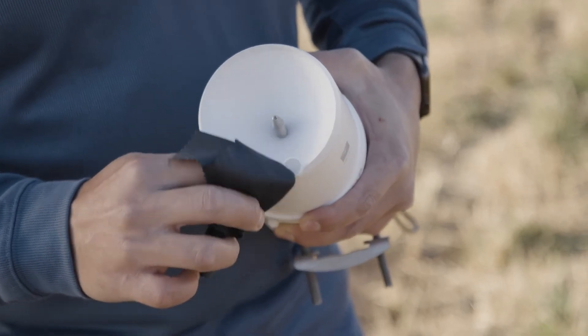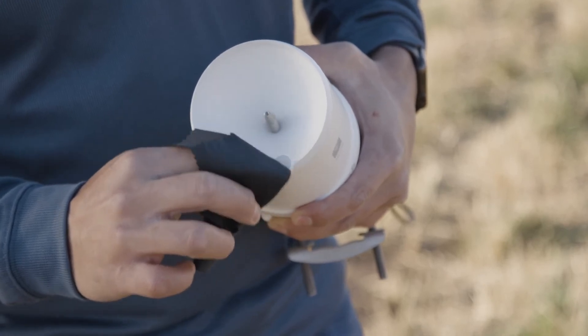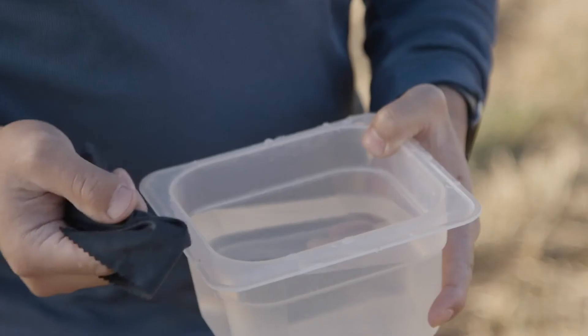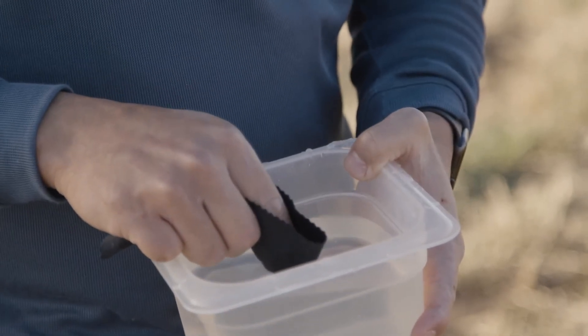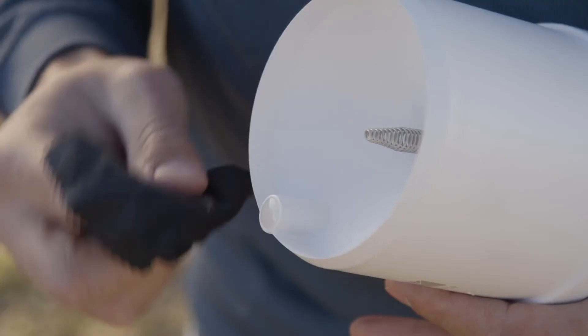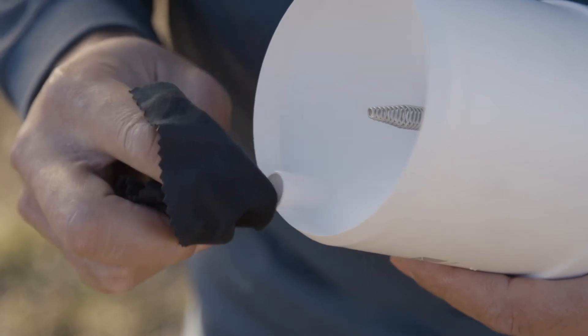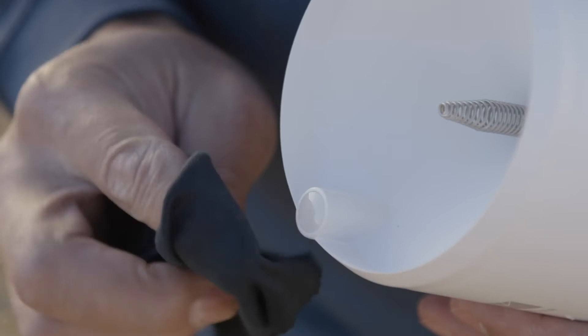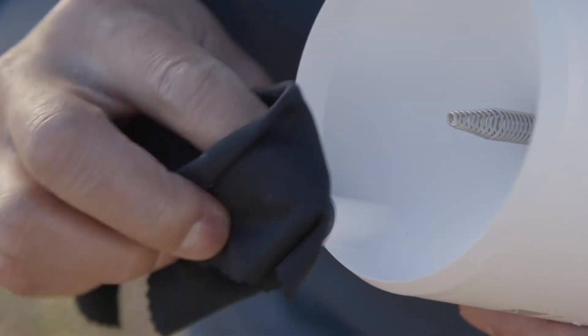Using a dry, non-abrasive lens cloth or other soft cloth, gently wipe the Atmos 41 pyranometer to clean dust off the sensor. If there is more debris than light dust on the sensor, such as bird droppings, then moisten a portion of a lens cloth with clean water and gently wipe off all debris. Stubborn contamination can be removed with diluted Windex cleaner if necessary.